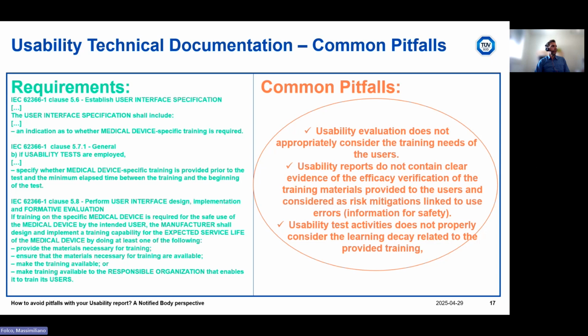In case of usability tests, in the usability test plan, the manufacturer shall specify whether a specific training is provided prior to the test, and if so, which is the minimum elapsed time between the training and the beginning of the test. This last requirement is related to the learning decay concept. So, let's say, simulating the real world, where the training maybe is provided in one day and then the first use of the device will happen after more than 1 month.